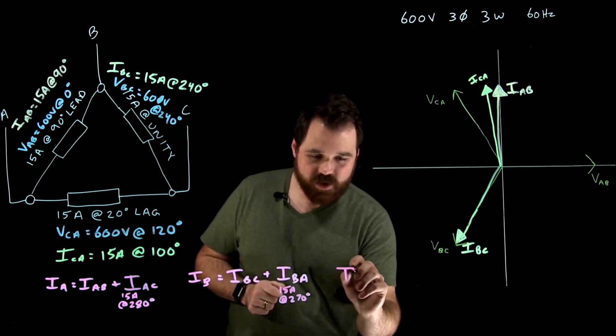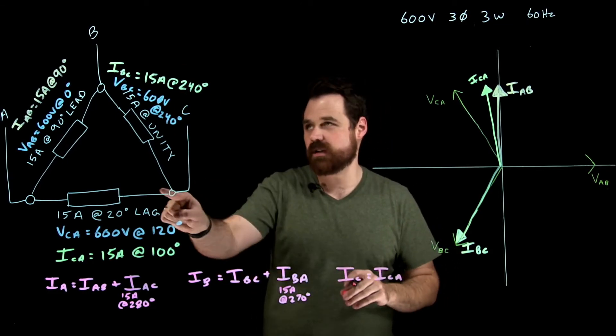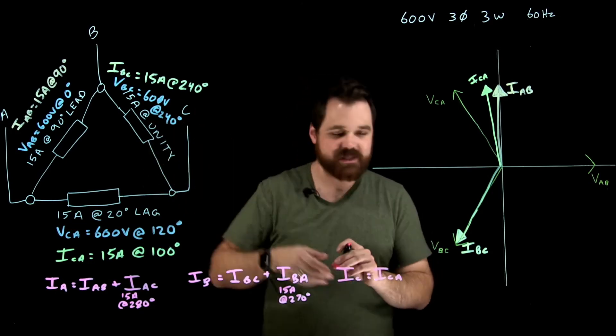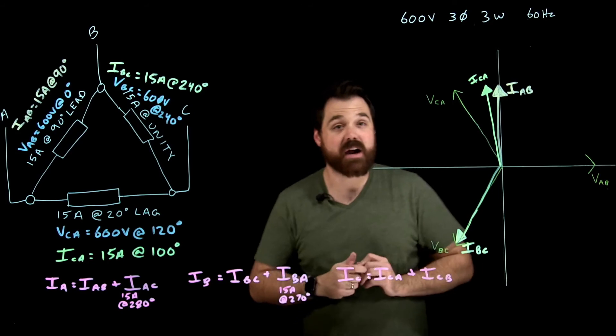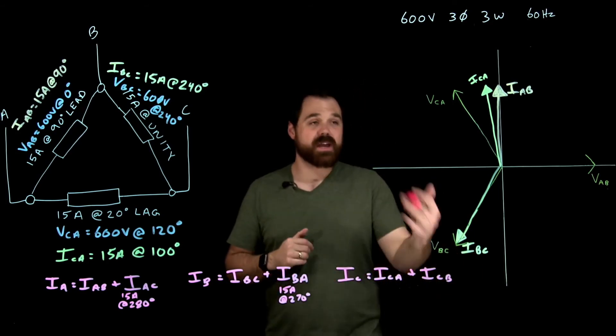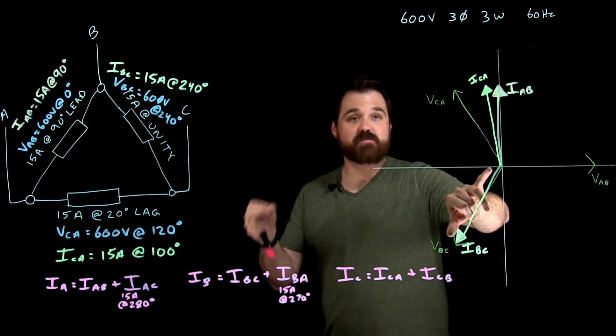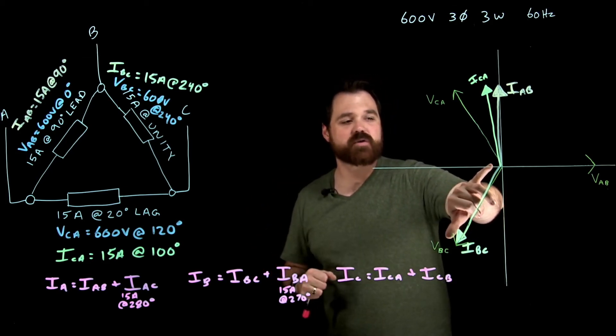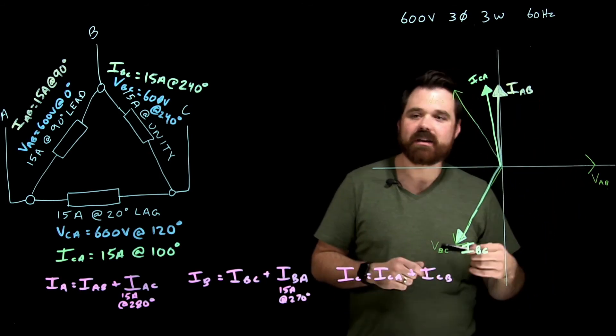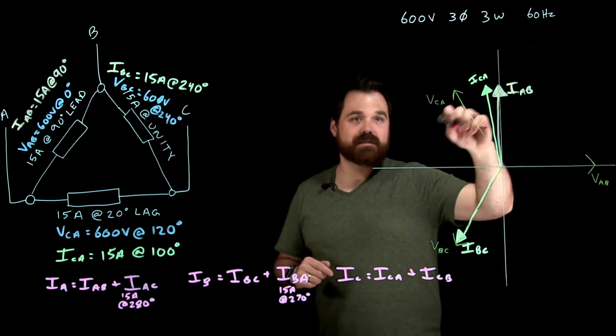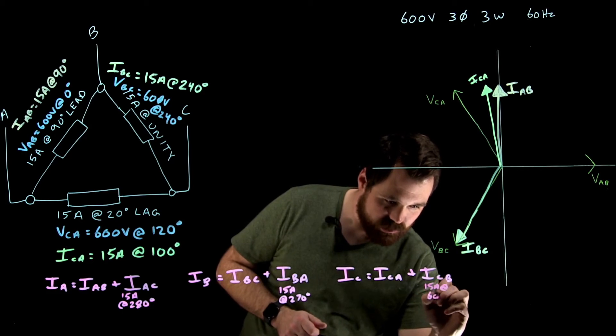We do the same thing for IC equals IC to A, comes in, here's IC to A, plus IC to B, which we are going to have to do the math for that. So again, IC to B we don't have right now, but we do have IB to C. And IB to C is at 240, which means IC to B is the exact opposite. So we will be minus 180, and it would be at 60 degrees. So this is 15 amps at 60 degrees.